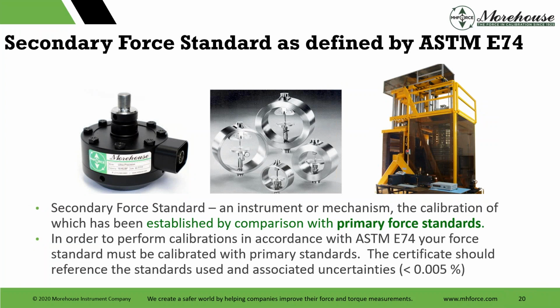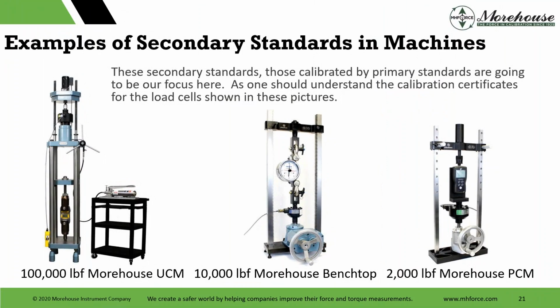Secondary force standard, that definition, an instrument or mechanism, the calibration of which has been established by comparison with primary force standards. In order to perform calibrations in accordance with ASTM E74, your force standard must be calibrated with primary standards. The certificate should reference the standard used, and the associated uncertainties should be less than 0.005%. Some examples of secondary standards. Those calibrated by primary are going to be our focus here.